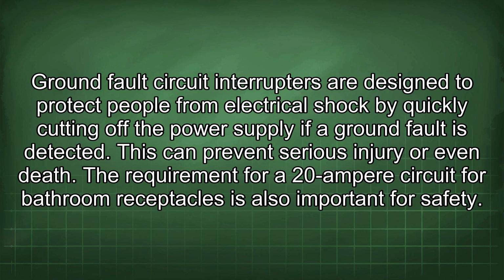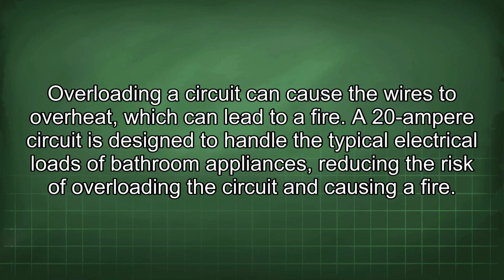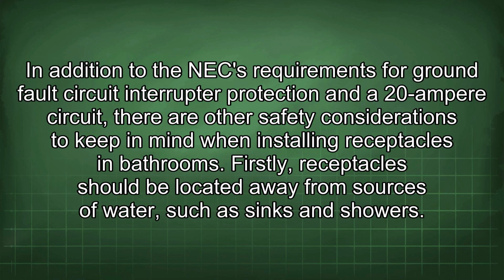The requirement for a 20 ampere circuit for bathroom receptacles is also important for safety. Overloading a circuit can cause the wires to overheat, which can lead to a fire. A 20 ampere circuit is designed to handle the typical electrical loads of bathroom appliances, reducing the risk of overloading the circuit and causing a fire. In addition to the NEC requirements for ground fault circuit interrupter protection and a 20 ampere circuit, there are other safety considerations to keep in mind when installing receptacles in bathrooms.